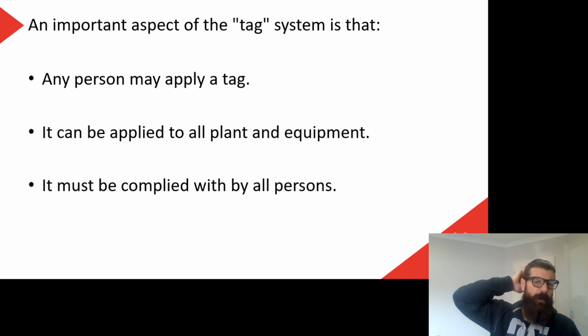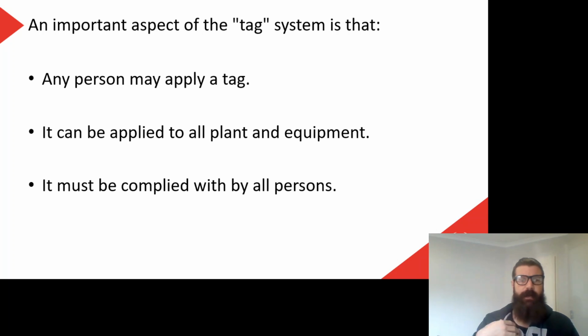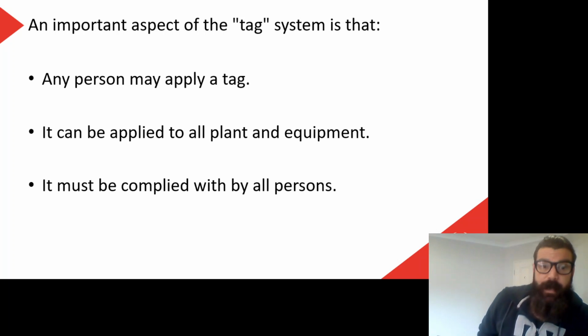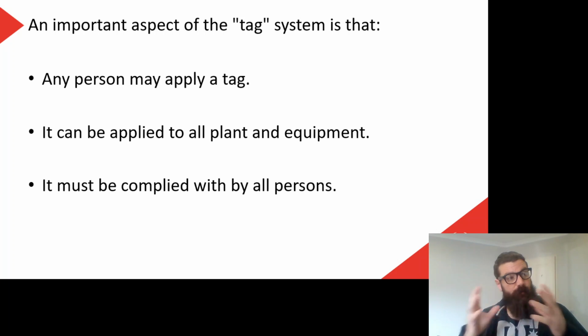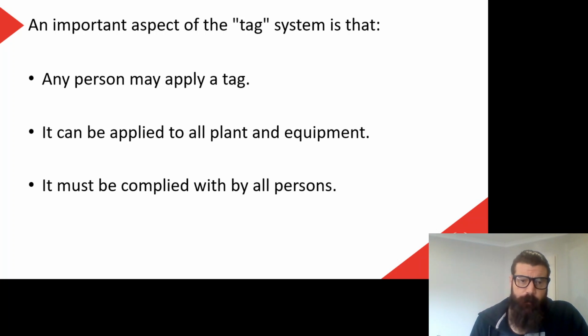Okay, so the important aspect of the tag system is that any person may apply a tag, and it can be applied to all plant and equipment, and it must be complied with by all persons. So anyone can put a tag on something. We've again talked about before, we might have multiple people working on something, and as I said on the last slide, it might not always be electrical. So I might tag something out because I'm doing electrical work on it, but then one of the mechanical guys might tag that same thing out because he's doing mechanical work, and we don't want that turned back on until both of us are finished.